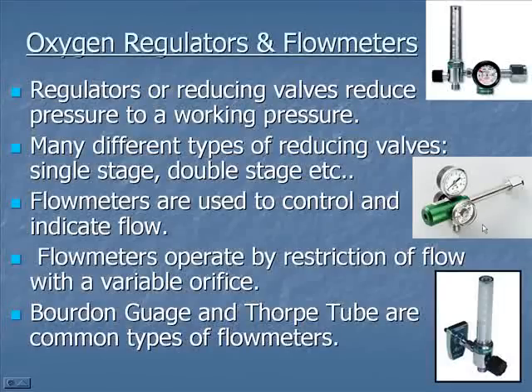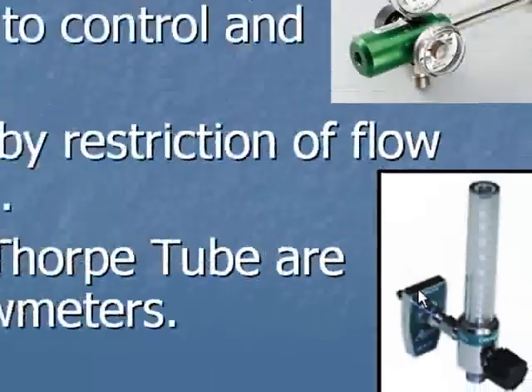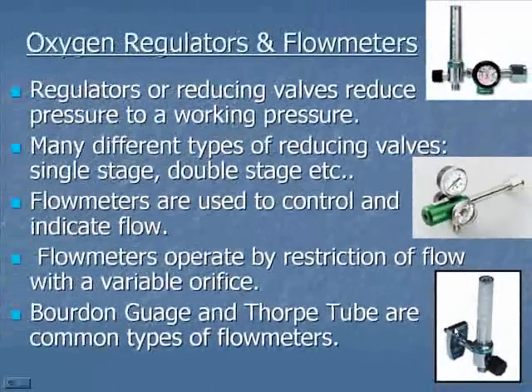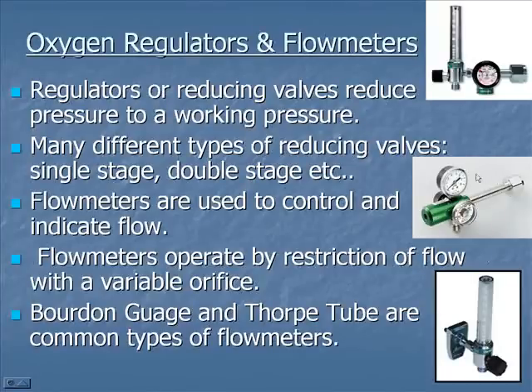There are different connectors — hospitals employ different types, so you have to pay attention to what connection system the hospital employs. A flow meter for wall connection is not going to connect to an E-cylinder. A flow meter for an H-cylinder requires the right kind of regulator.